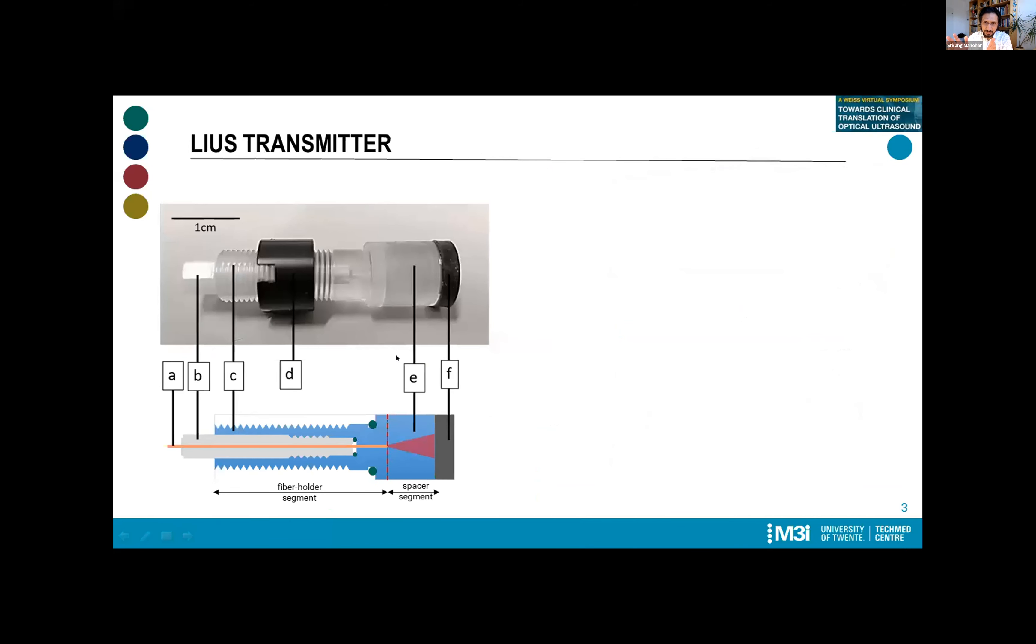Let's go immediately into what such a LIUS transmitter looks like. Here's a photograph and here is a schematic. We have a LIUS absorber which is mounted onto a segment which we call the spacer segment, which in turn is mounted onto what we call a fiber holder segment. All of these parts are made from clear perspex. The fiber holder arrangement can accommodate a chuck which can be screwed in, and that carries an optical fiber. We use a 600 micrometer multimodal fiber. This entire assembly can be fitted with nuts and a screwing arrangement with O-rings to make a watertight seal in the imaging tank.